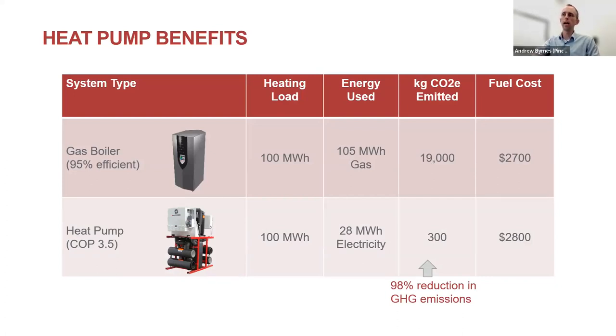If you compare a gas boiler with a heat pump, a gas boiler being 95% efficient and a heat pump being 350% efficient, or with a COP of 3.5 - if you were to service a similarly sized heating load for both, a gas boiler might use 105 megawatt hours worth of gas, where a heat pump uses 28 megawatt hours of electricity.